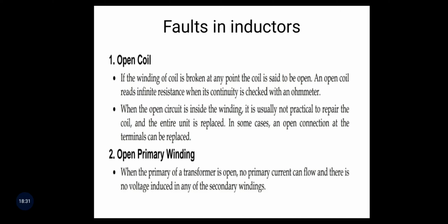When the open circuit is inside the winding, it is usually not practical to repair the coil, so the entire unit is replaced. In some cases, an open connection at the terminals can be repaired. That is an open coil.